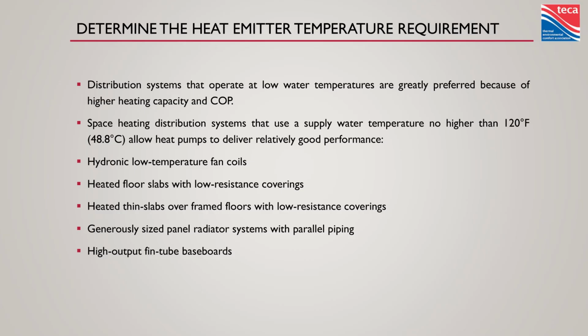So you start with a heat loss calculation, figure out what you have in room by room loads, figure out how you're going to address those with your heat emitters and what water temperature they're going to need, and then you can start to pick your heat pump because the capacity of that heat pump is going to change based on that water temperature.